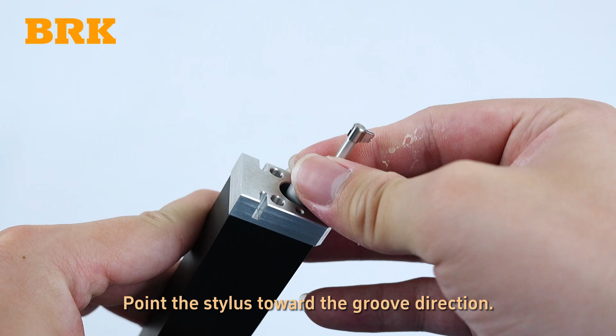Tap Settings and select Measurement Settings. Sampling Length: select based on the roughness value range. Evaluation Length: generally select X3 or X5. Range: generally select positive and negative 20 µm or positive and negative 80 µm. Return to the measurement screen.